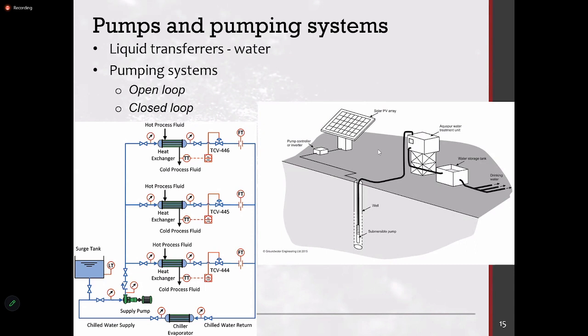if it is not a closed loop system, and you are circulating only one side, then you have to give the water head as well, because there's a head difference. But in a closed loop system, there is no head difference, because you are getting the same water back to the pump and you're only circulating. So it is only a head loss that you have to provide from the pumps actually.